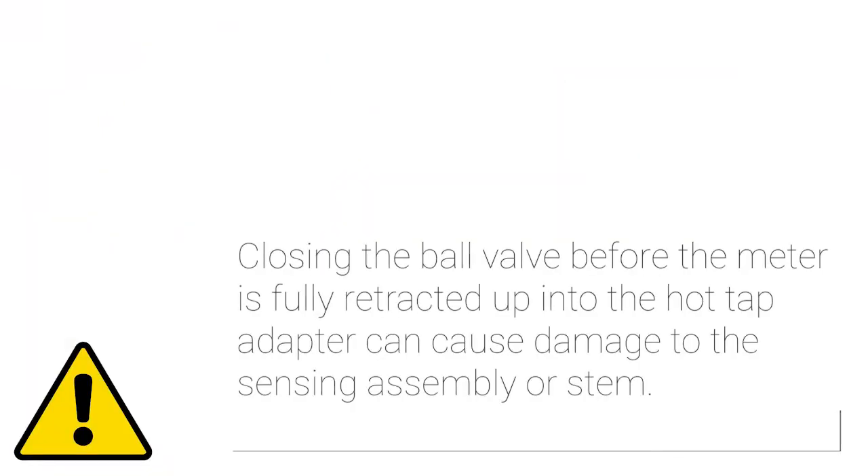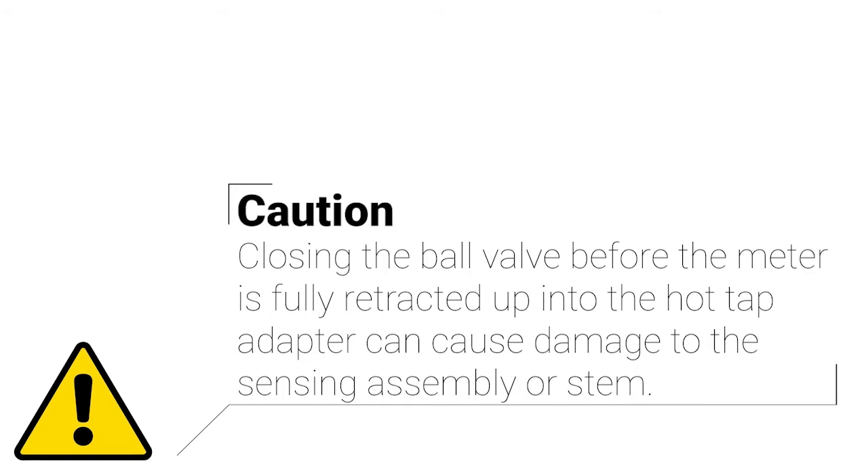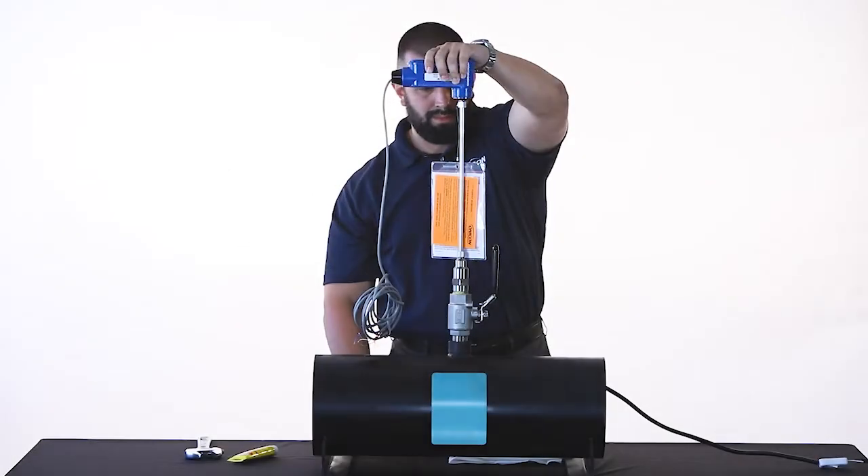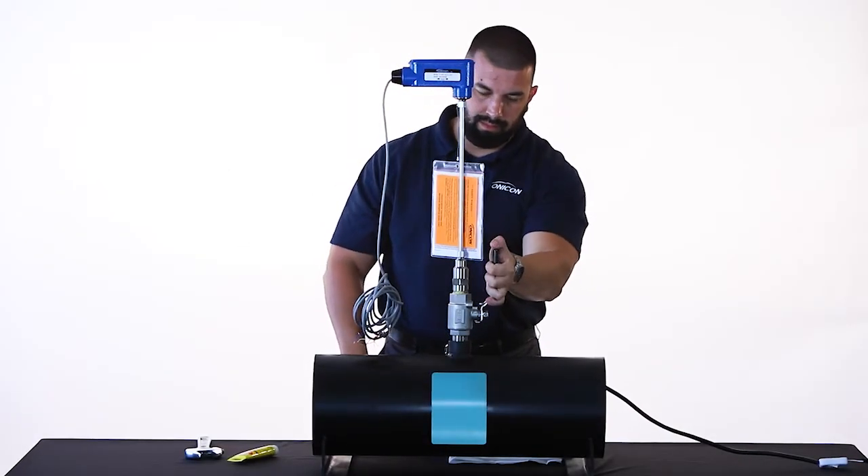When fully retracted, the sensing assembly will hit a metal stop inside the hot tap adapter. Closing the ball valve before the meter is fully retracted up into the hot tap adapter can cause damage to the sensing assembly or stem. Gently close the ball valve to isolate the line.